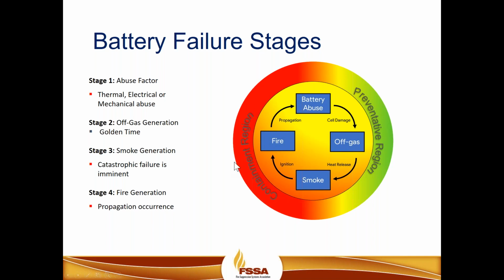As we move to the second stage of battery failure, this is really that, going back to that term, that golden time that the South Koreans had coined. This is where off-gas generation occurs. And really, it gives us the opportunity to provide, as an industry, solutions in off-gas detection. So there's several different type of technologies out there for off-gas monitoring, and it's becoming more widely used and accepted as a standard practice for early warning detection. The third stage is the smoke generation stage. And of course, once you reach this particular stage of smoke generation, catastrophic failure is imminent.